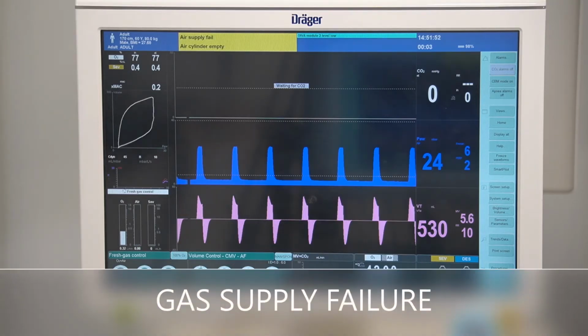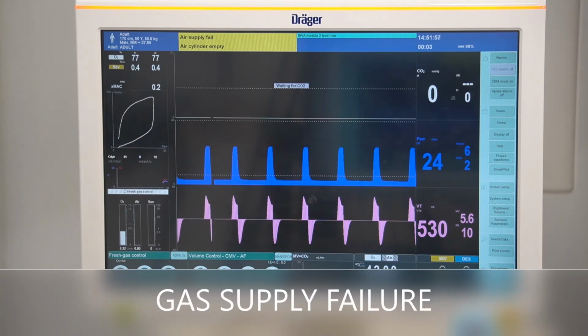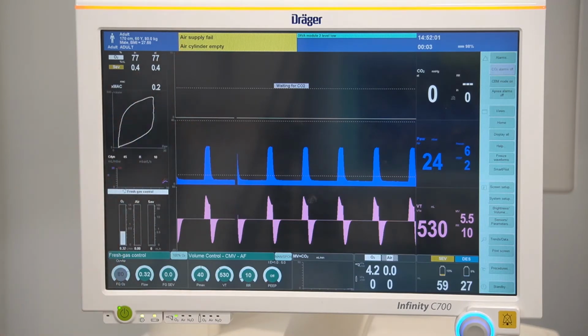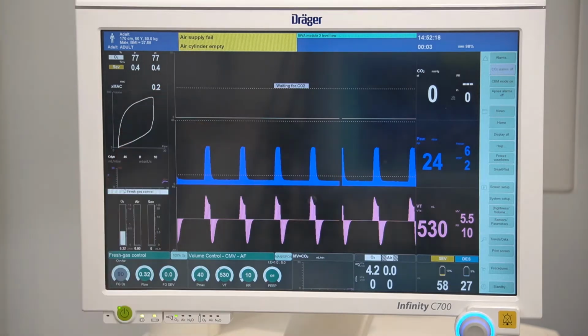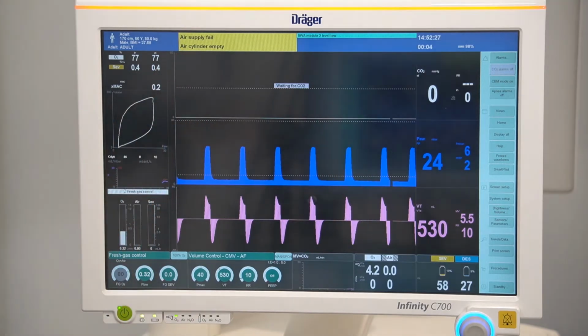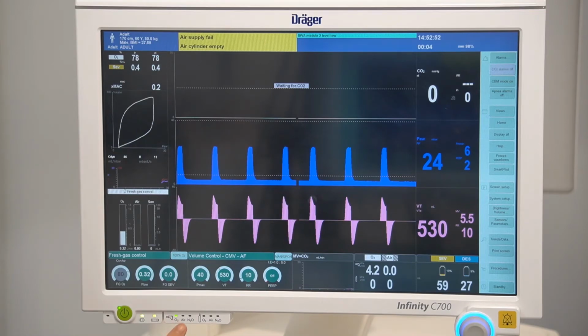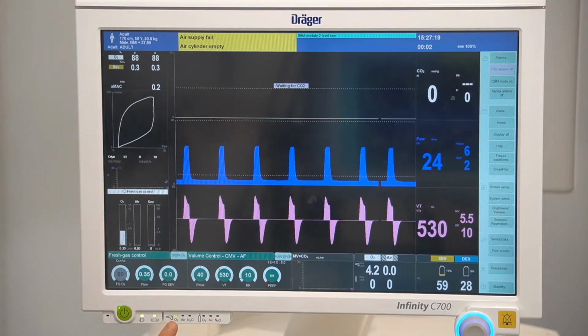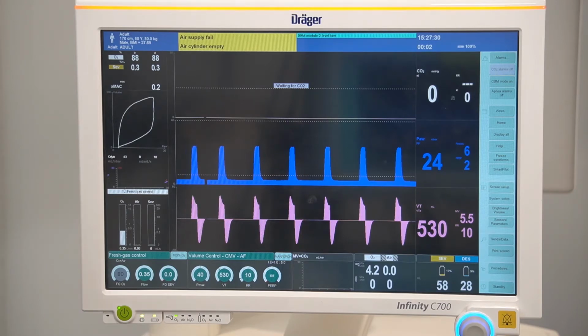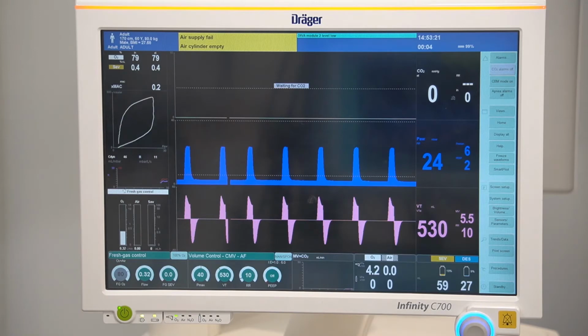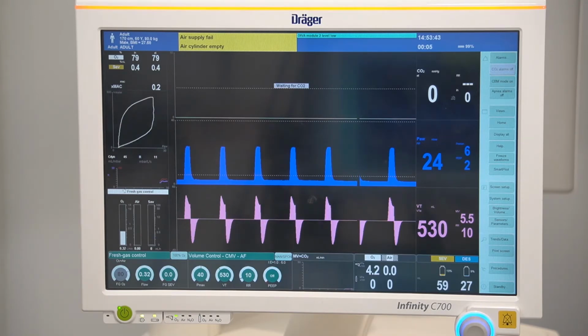In the event of gas supply failure, an alarm message will appear stating the specific gas that has failed. In this instance, there is central air supply failure and the reserve air cylinder is empty. You'll also see it reflected in the LED light indicators. There is an absence of an LED light above central air, and there is no light above reserve air cylinder. If your central gas supply fails, this will then prompt the user to open up the corresponding reserve gas cylinder. You will be able to verify the remaining capacity on your Zeus screen. Given that there is no air supply, the device will default to 100% oxygen. In the event of oxygen failure, the device will deliver air.